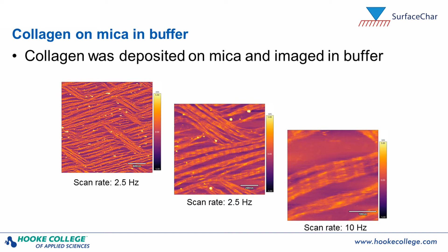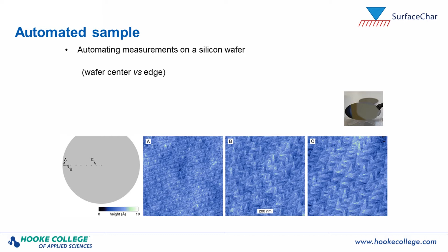And I just want to end with a couple of slides showing the high resolution that this large sample instrument can achieve. If you remember from one of my earlier slides, one of the drawbacks of a large sample instrument is the ability to get high resolution, because all the work and the detection and the motion is being done by the tip, so it can be very noisy. And here's a nice example demonstrating on a silicon wafer, a very smooth silicon wafer. So notice what our Z-scale and height here is. It's only 1 nanometer. And they've moved to different points on the wafer from the very edge, now down all the way to the middle, which can be done now, even though this is a large 200 millimeter wafer. You can see the structures changing at the wafer center versus edge with these very fine Z resolution, being able to pick up only a few angstroms in height change all across the surface.